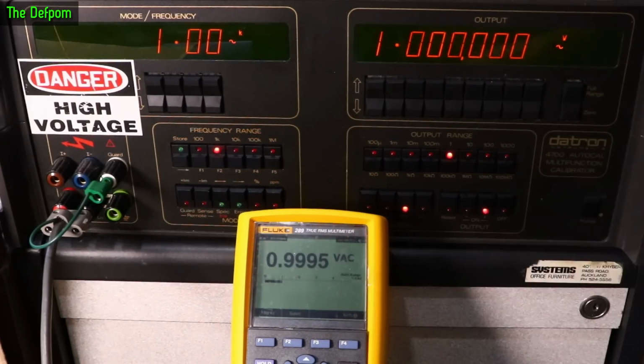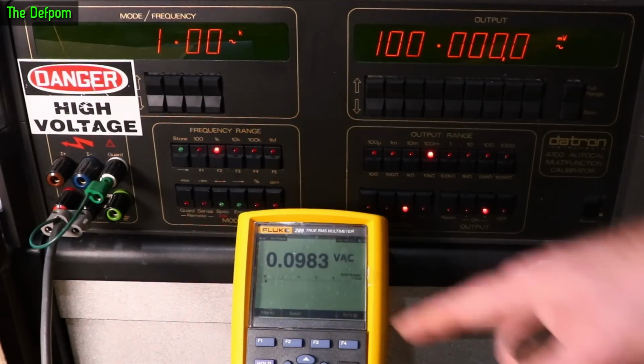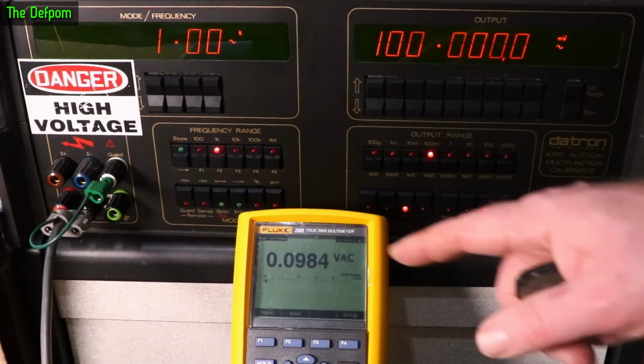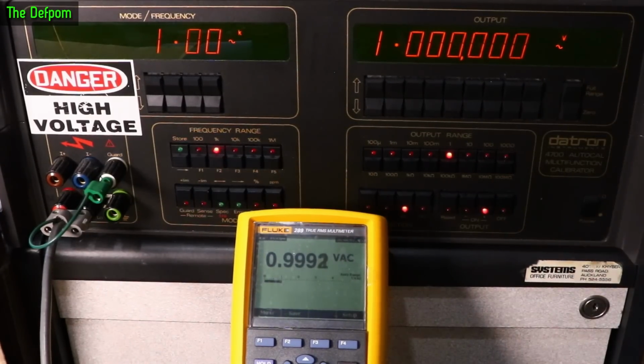1 volt is about 5 counts down. And back down to 100 millivolts, which we saw before, is a couple of counts down there. Well, 20 odd counts down, something like that. Let's try different frequencies. Go back to 1 volt. And I also look at the frequency response on this thing, and I always do this at 1 volt. This is a nice reference voltage. Should be enough for it to sense properly without being overdriven and inducing other problems.